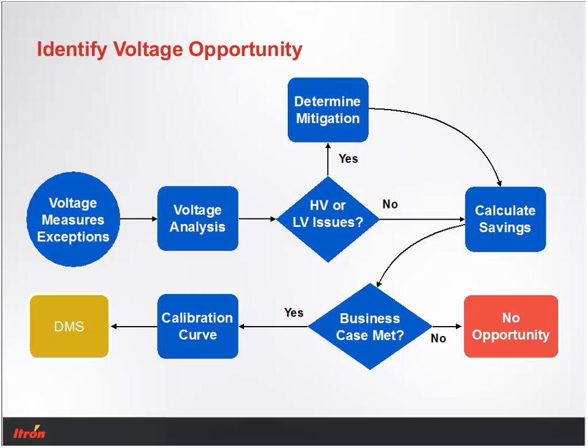At that point, we look at whether we've met our hurdle rate, yes or no. If we haven't, then this feeder—and we do this feeder by feeder—has no opportunity for savings. If the feeder does meet the business case, then the next step is to calibrate the savings: where precisely can we go with our set point for the DMS? That means, what will our target voltage for that end of line be? What are we going to set that for? What is that target?